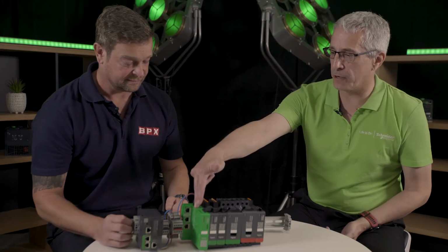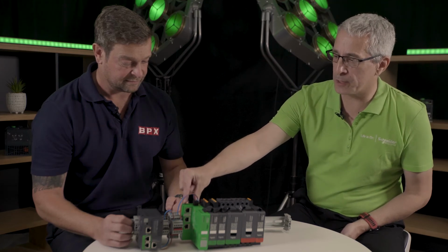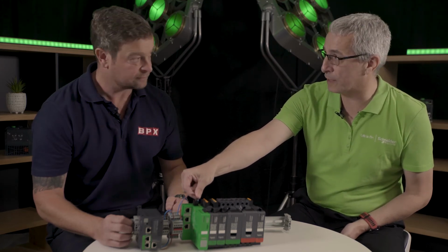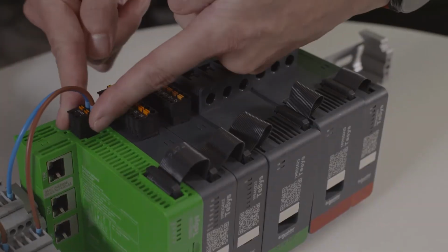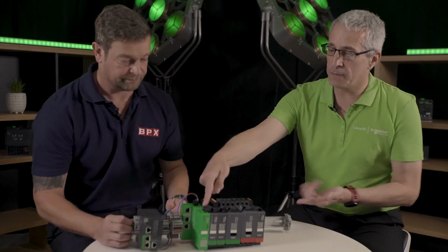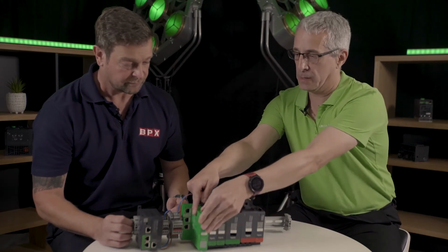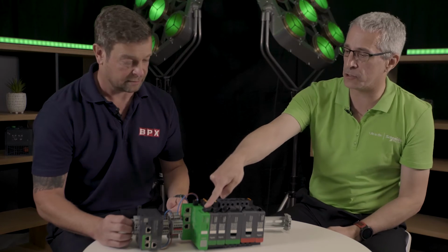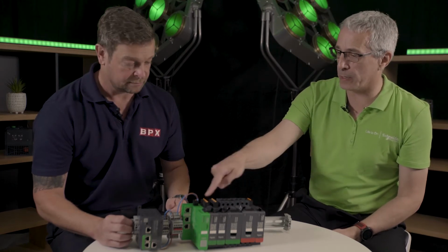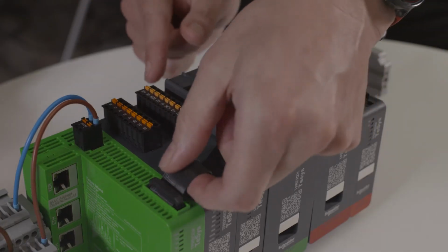TeSys Island will have many features and benefits. One that stands out for me at the moment is I can see very few wires, only a ribbon cable. Why is that? Yeah, so it's a benefit in terms of installation time, the amount of wiring it needs to actually build the panel. So you've got a whole series of starters here with a bus coupler over on the right-hand side. As far as the bus coupler is concerned, you've got a single 24-volt DC feed into it, and you've got an Ethernet connection back to the PLC. The individual modules are just connected with this ribbon cable that you can see just plugs in, and you end up having a connection across here. That connection is the communication, plus the 24-volt feed for the coils on the individual contactors.